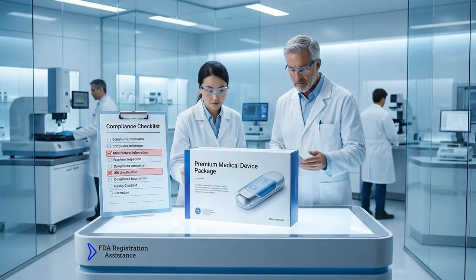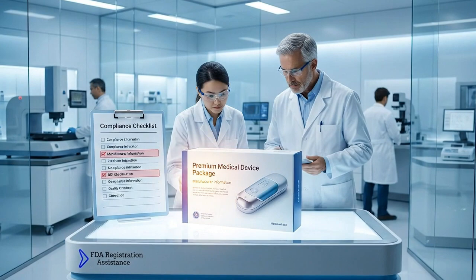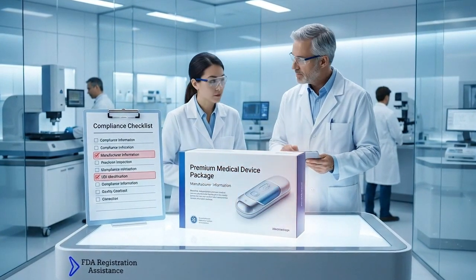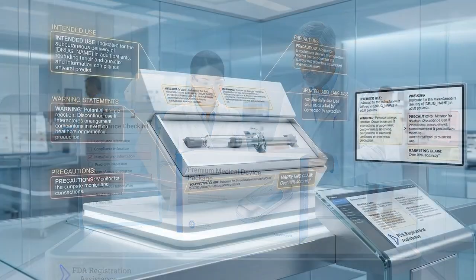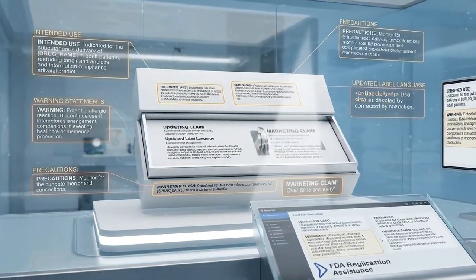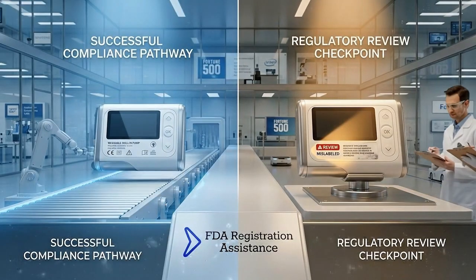Some of the most common medical device labeling issues include missing manufacturer information, improper UDI implementation, inconsistent intended use statements, missing warnings or precautions, outdated labeling language, and promotional claims that exceed regulatory authorizations. These mistakes can create compliance concerns even when the device itself is otherwise compliant.